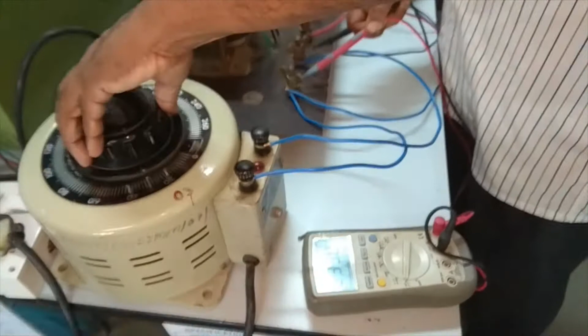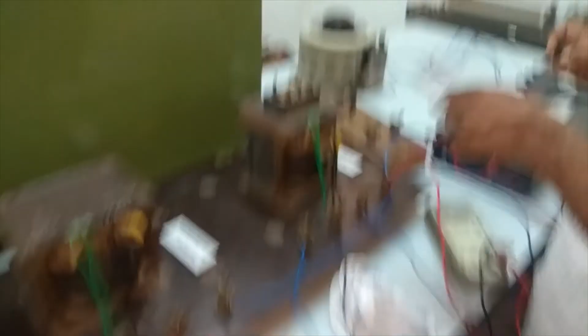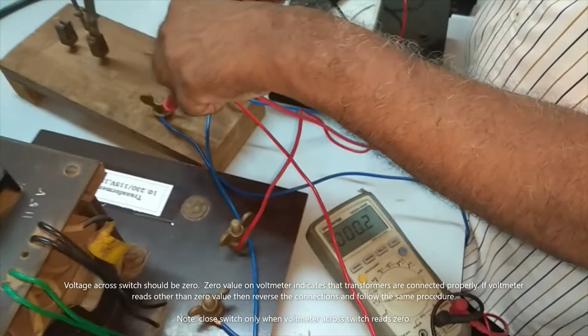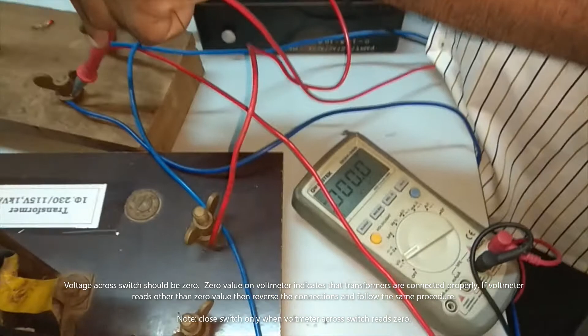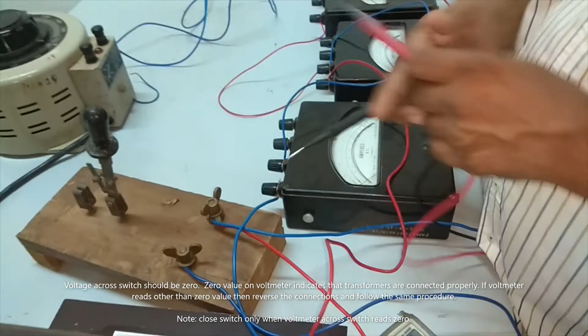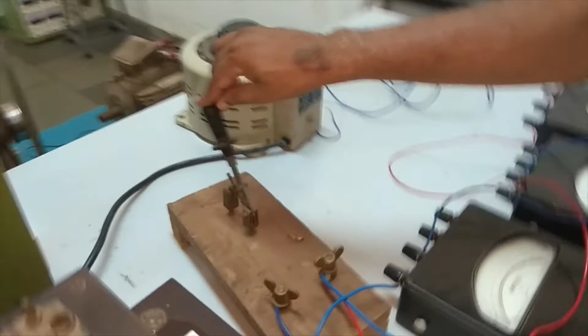After making the connections, we will switch on. We have switched on, and are adjusting the supply voltage to 230 volts for the first transformer. The variac is connected to the HV side, that's why we kept it at 230 volts. Now we are measuring the voltage across this switch, which indicates whether the transformers are properly connected in parallel or not. We can observe it is 0, so yes, it is connected properly. Now we can switch on this knife switch.